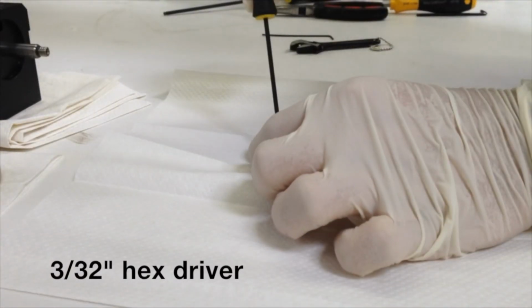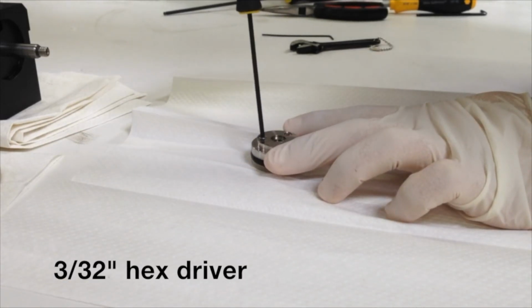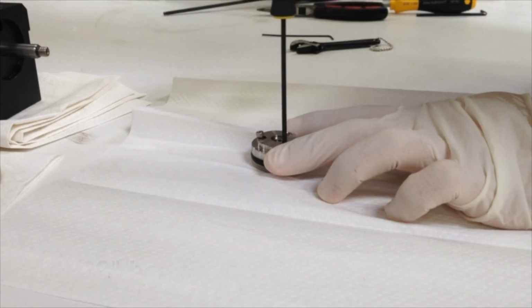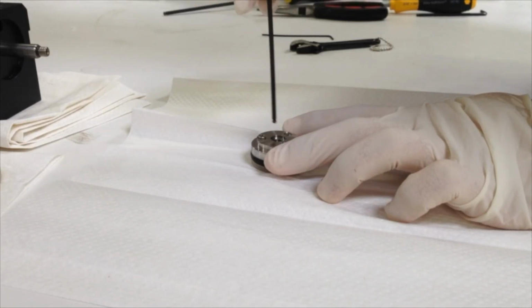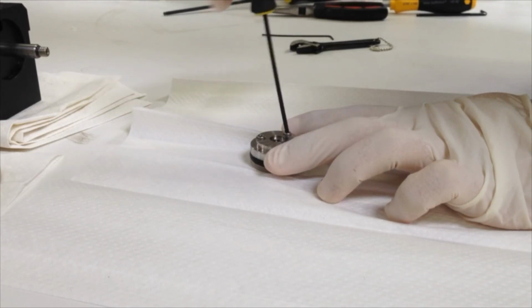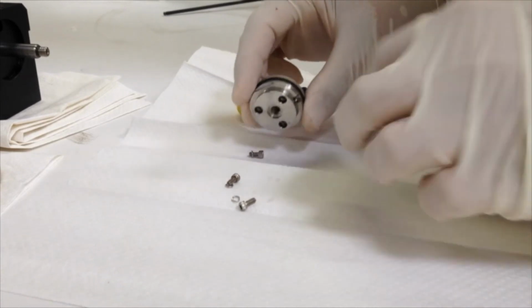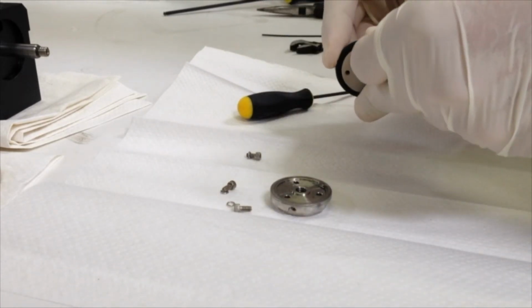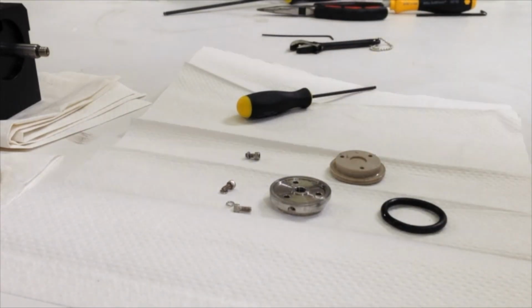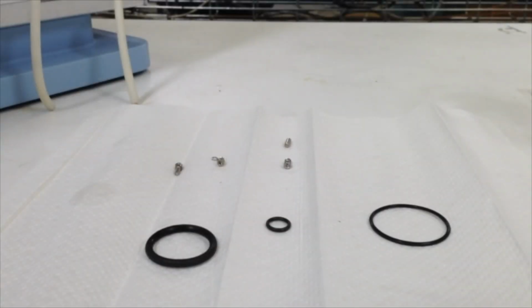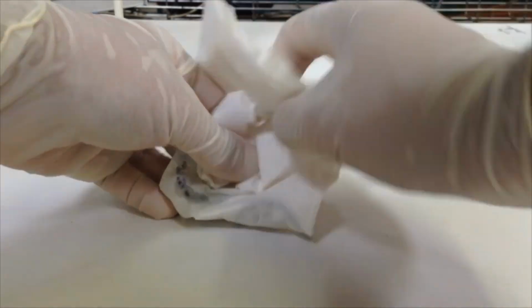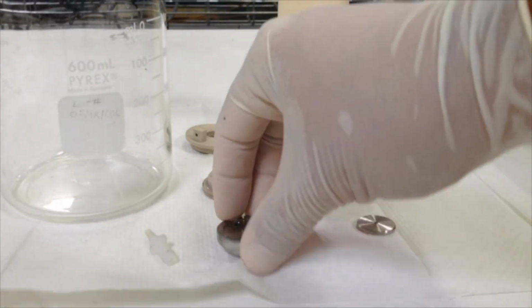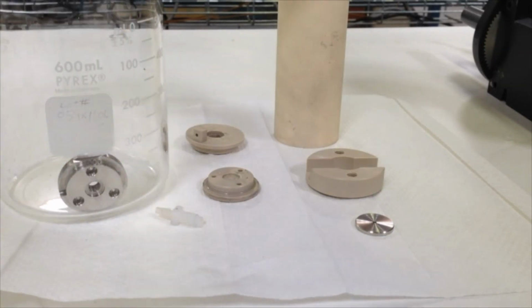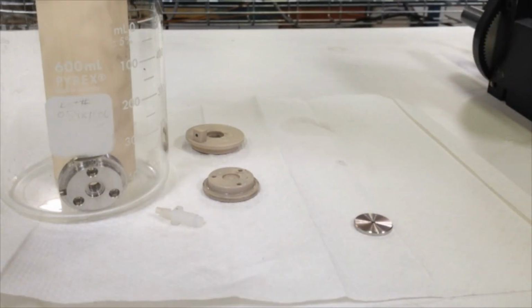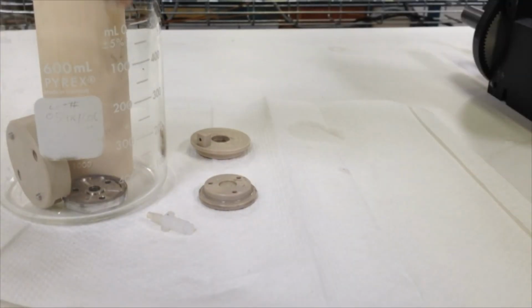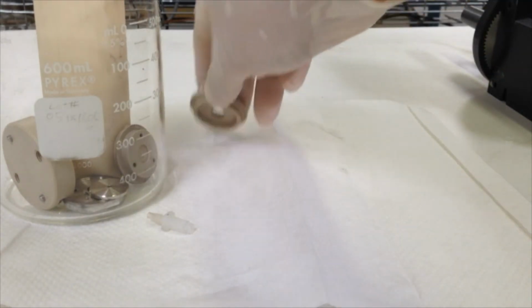Using a 3/32 inch hex driver, completely remove the 3 screws and washers holding the PEEK piston head to the metal piston face. Do not reuse these 3 screws and washers. Dispose of the old O-rings and screws used inside the pump. Place the metal piston face, ceramic cylinder, pump cap, PEEK piston head, piston O-ring guide, piston wash connector, new seals, and screws into a clean beaker.